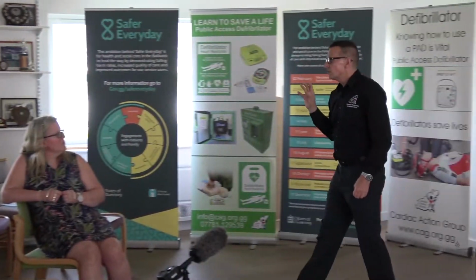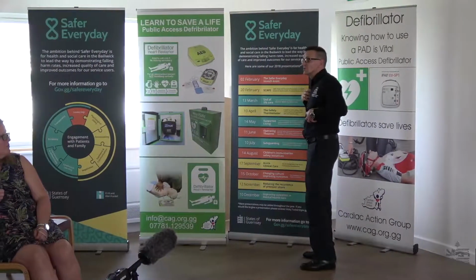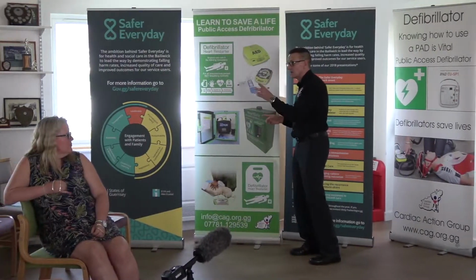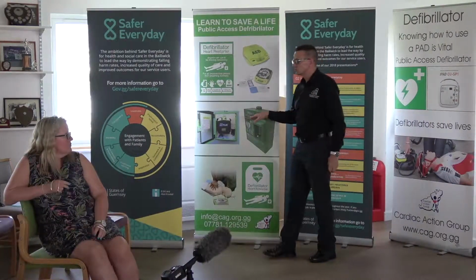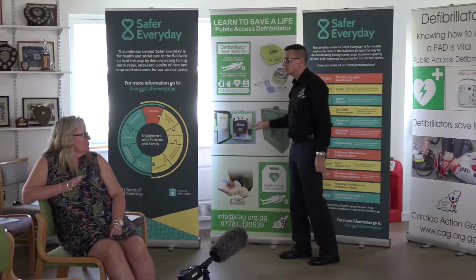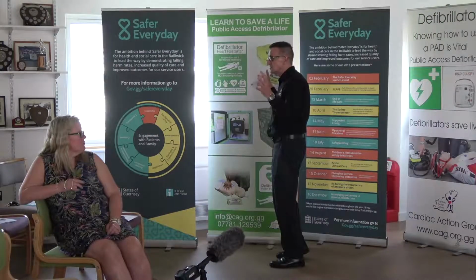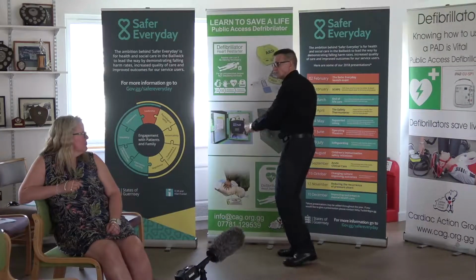But not only that, what would happen if they opened the door and the defibrillator didn't work because nobody checked it properly? So I've gone around every single one of our 37 public access defibrillators, and I'm now going around the private ones that are inside people's buildings, and I'm making sure that the pads are in date, the batteries are in date, because the only maintenance for one of these is every 5 years you need a new set of batteries and a new set of pads, £115, and that's it for 10 years. 5 years for the battery and pads, the defib will last 10 years.